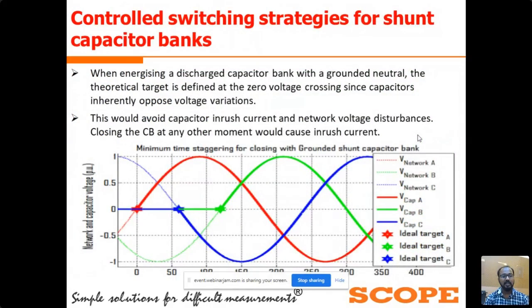So for the capacitor bank application, our electrical target points are the system voltage 0 points. Here in the waveform you can see the R phase, Y phase, and B phase waveforms. For the capacitor bank application, taking the reference of the R phase waveform, we can take the target angles 0 for the R phase closing, 60 degrees with reference to the R phase only. We can take the reference angles 0, 60, and 120.